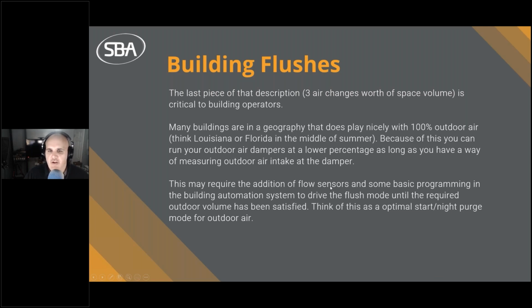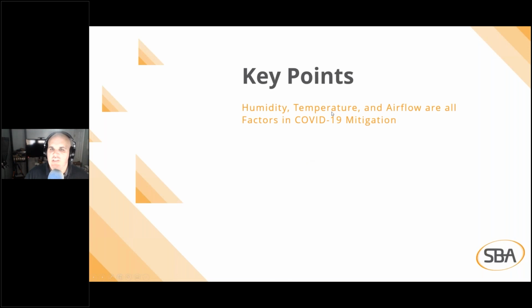Now, this may require the addition of some flow sensors, some basic programming in the building automation system to drive the flush mode until this outdoor air volume has been satisfied. So I like to think of this as like an optimal start or night purge mode, but just for outside air instead of temperature. All right, so the key points on this: humidity, temperature, and airflow are all factors in COVID-19 mitigation, at least based on the studies.